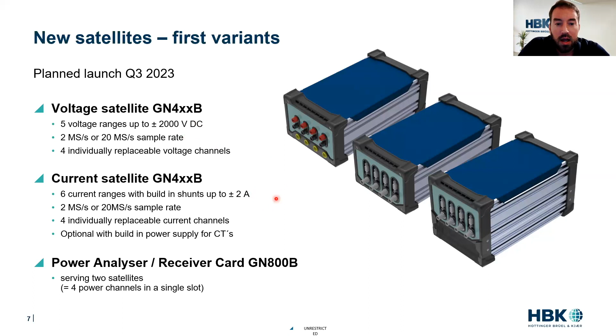If you really want to get into the hairy details on some of those inverter behaviors, that same really high accuracy applies. In practice, you'll have your little box sitting right next to the measurement, with super short measurement cables so you're not picking up EMC or electric noise. You'll have a current box that sits right next to your current sensors and powers them, again with really short cables to minimize EMC exposure.